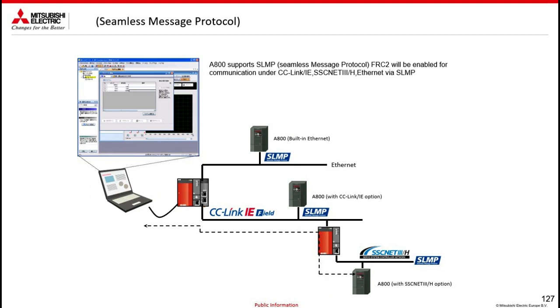There is also the possibility to use SLMP functionality, mainly to be able to connect to the software. You have to keep in mind that you can connect from software to inverter in different ways. You can connect via USB cable, which is certainly easier. You can connect via serial, for example in the case of the FR-D700, because for the others it would not make much sense to go through the trouble of connecting via serial rather than via Ethernet. By connecting via Ethernet, you can also go through a PLC. For example, if you have installed PLC inverter communication, you can easily connect to the PLC, which will act as a bridge to connect to the inverter.